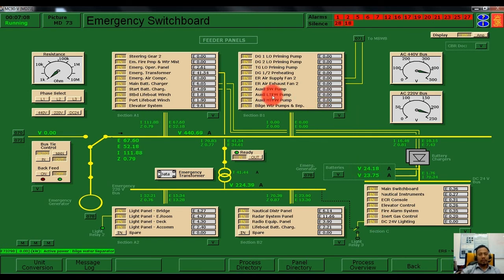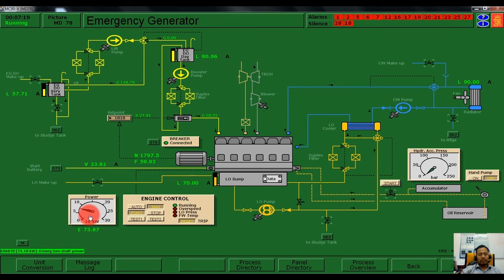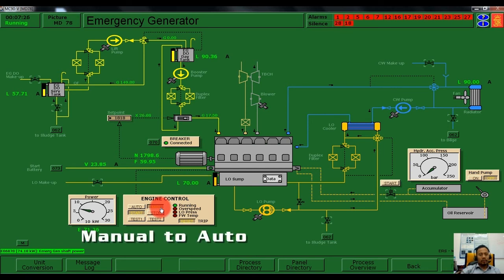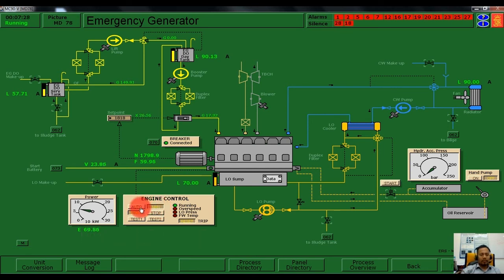After connecting the emergency generator to various equipment, we need to go back to the emergency generator. Currently it is in manual mode, so we need to change the mode from manual to automatic. This is very important because if our ship has a total power failure, the emergency generator will switch on automatically.